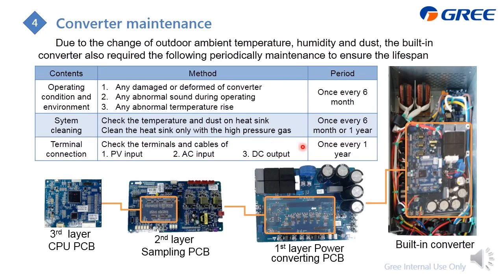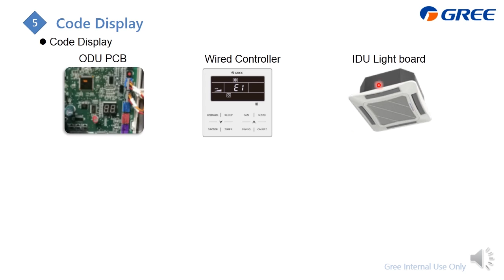Next part is the basic troubleshooting. First is how to check the code. The code will display on these 3 devices: outdoor unit PCB, this LED, or wire controller. Here we will also display the code, and if the inside unit is, for example, the cassette type, it will also display the error code on the light board. And here are the maintenance tools you may use during maintenance, including the multimeter, the current meter, the screwdriver, and this is the megameter.